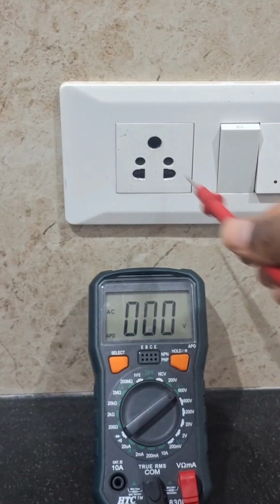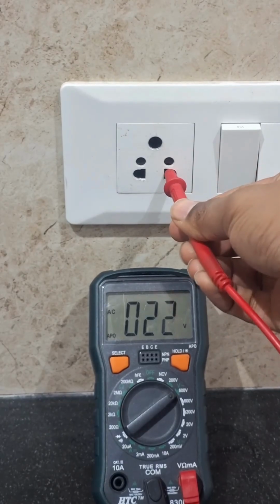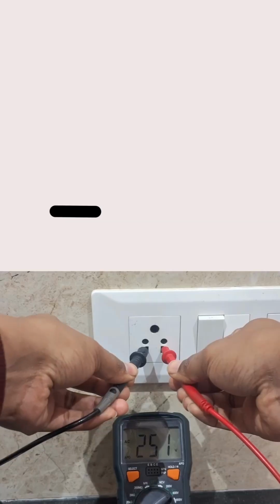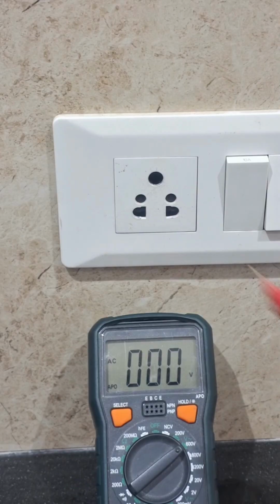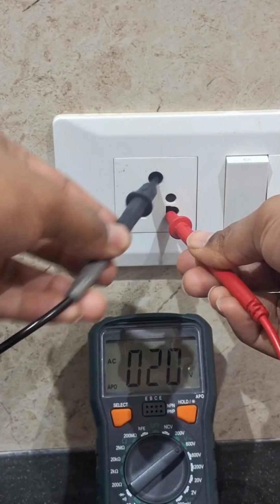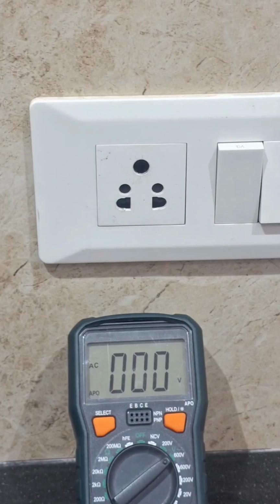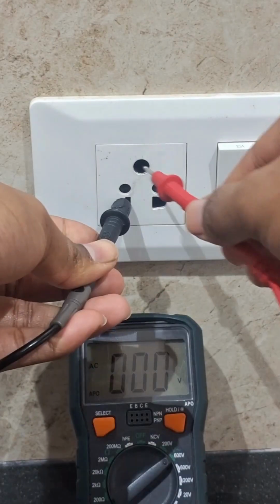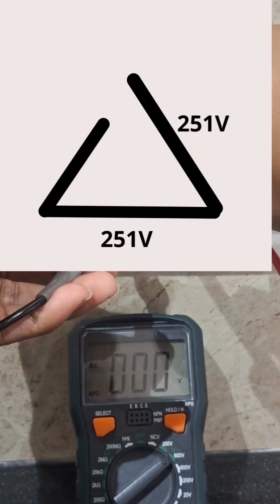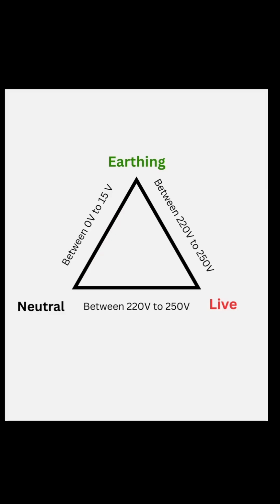Step 2: insert one probe in the right hole and another in the left, and note it down. Step 3: insert one probe in the right and another on top, note it down. Last, one probe in the left and another on top, note it down. If you get values like these, it means you have the live wire on the right, neutral on the left, and earthing is available, signifying that your socket is in good condition.